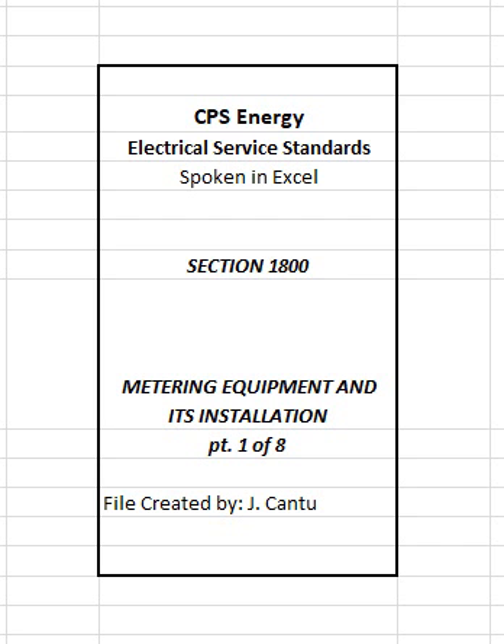Exception 2. When gutters, etc., are opened or unsealed by CPS Energy for customer work, customer is responsible for providing a one-time lock to safely secure meter covers, gutters, etc. Refer to Article 1808(7). CPS Energy will remove one-time lock and inspect all work before installing approved lock and/or seal.